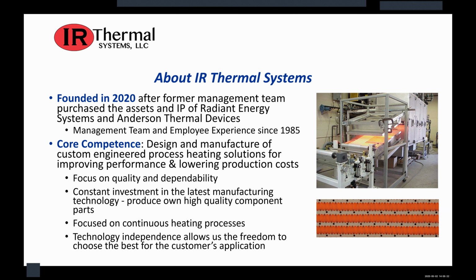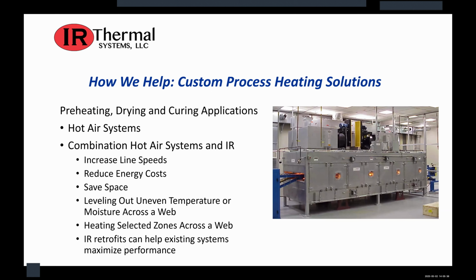We're focused on continuous heating processes, and we're also technology independent, and that allows us the freedom to choose the best technology for the customer's application. That means we do both hot air and infrared heaters and dryers. So what we focus on mostly are preheating, drying, and curing applications with hot air systems and combination hot air and infrared systems. Our systems increase line speeds, reduce energy costs, and save space. We level out uneven temperature or moisture across the web. We can heat selected zones across the web, and we also provide infrared retrofits that can help existing systems maximize performance.